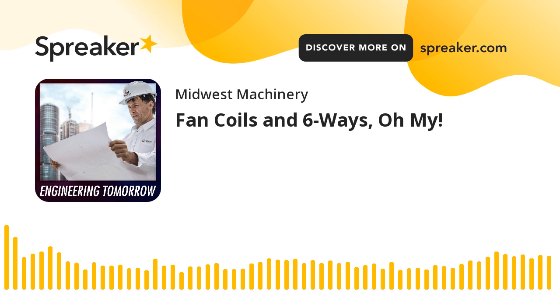So here now we're talking about moving air, and typically you're not going to find fan coils and VAVs on the same job. That's correct. Normally, VAV products are primarily for either non-heating or heating applications. They do not come with condensate drain pans in them, and that would matter if you had cooling inside your room, and you'd have to have a very tight envelope, and by envelope meaning your building had to be extremely tight and not with a lot of air leakage going in the doors or through the windows or anything else, because that could cause issues. But from the heating side, that's not so much of a problem, but it would be on a cooling side. But yes, VAVs are all for heating and just air movement, air distribution.